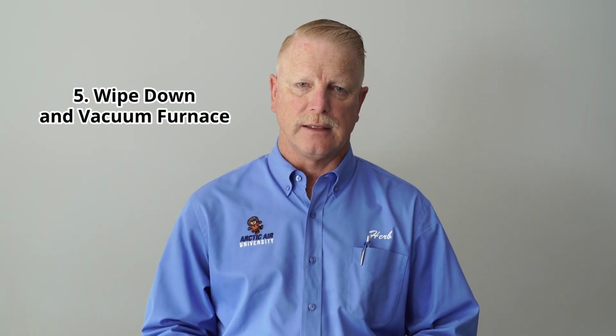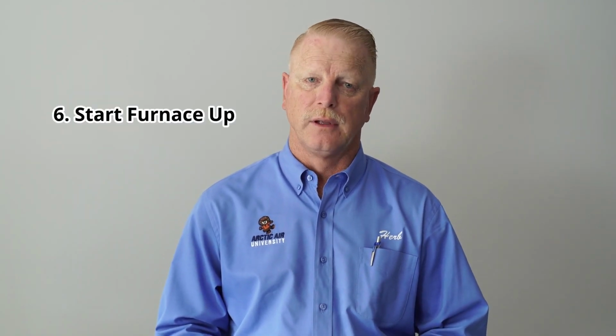After that, we will wipe down the furnace and vacuum any debris that may have collected inside that furnace. Then we're going to start the furnace up. Watch it run, see those burners fire up, make sure they stay in their proper position once the system is up and running. Then we'll do a carbon monoxide test around the furnace, and after a few minutes of runtime, we're going to come up into the living space and make sure there's no CO up in your living space. And then cycle the system off and watch it finish its operation. That's about it for our heating for a warm air furnace.